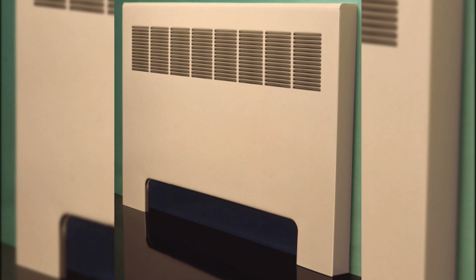E. In areas with frequently opening, closing doors, terminal units, door air curtains, cabinet unit heaters, convectors, must be supplied with a 30% propylene glycol water mixture from the primary dual-temperature water loop when chiller heaters are utilized. 2. Toilets. A. Toilets on the building's perimeter, top floor, or on a slab on grade must have terminal heating capacity.